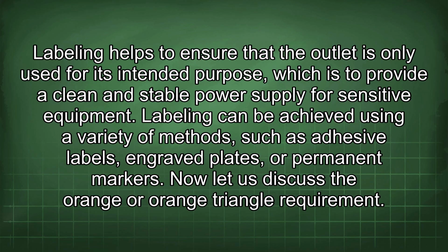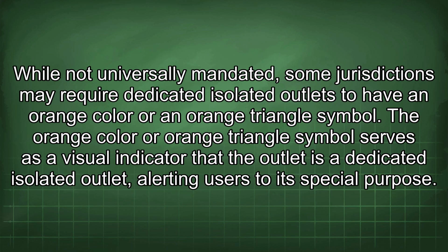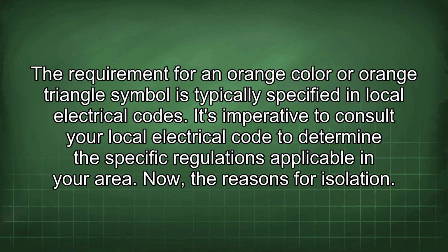Now let us discuss the orange or orange triangle requirement. While not universally mandated, some jurisdictions may require dedicated isolated outlets to have an orange color or an orange triangle symbol. The orange color or orange triangle symbol serves as a visual indicator that the outlet is a dedicated isolated outlet, alerting users to its special purpose. The requirement for an orange color or orange triangle symbol is typically specified in local electrical codes. It's imperative to consult your local electrical code to determine the specific regulations applicable in your area.